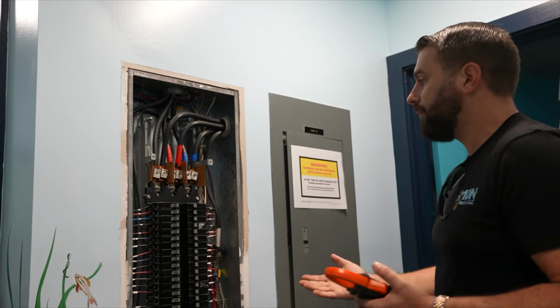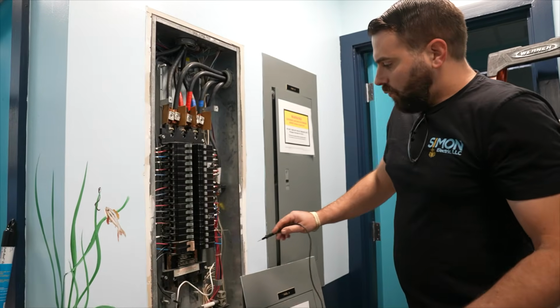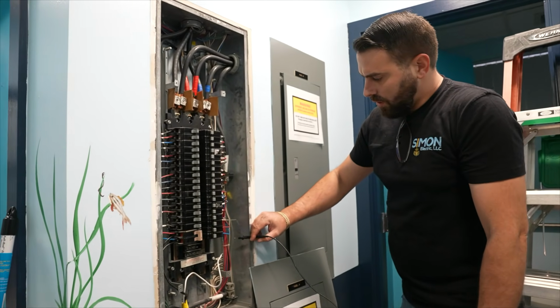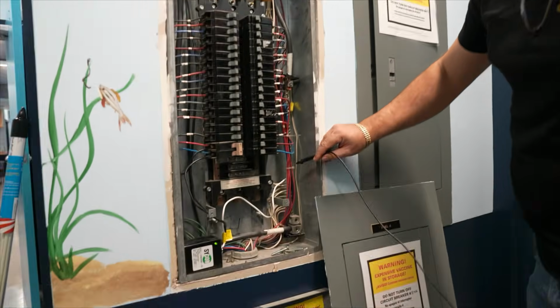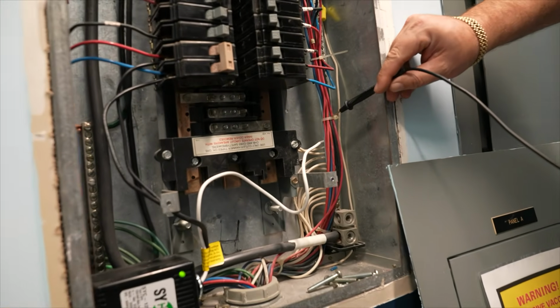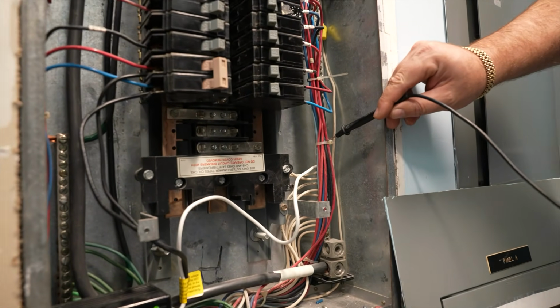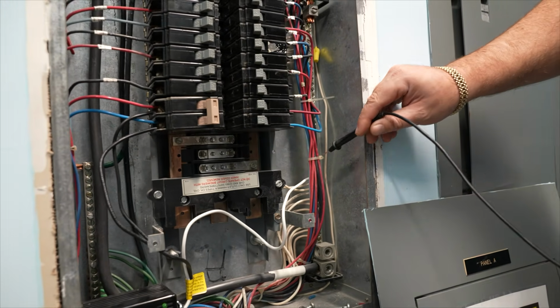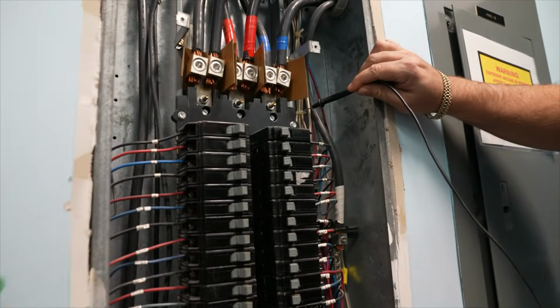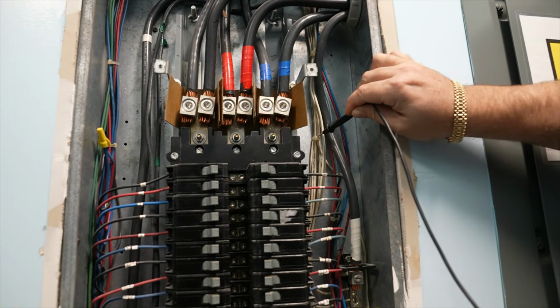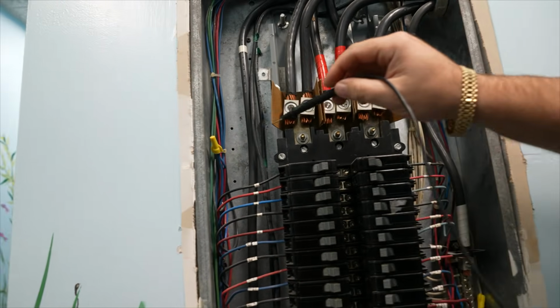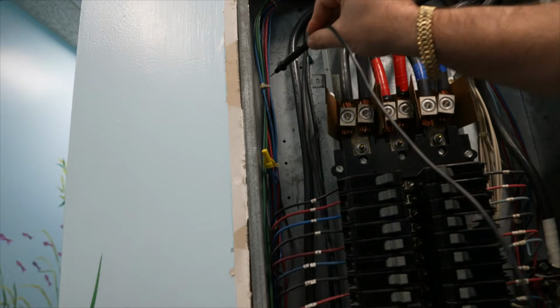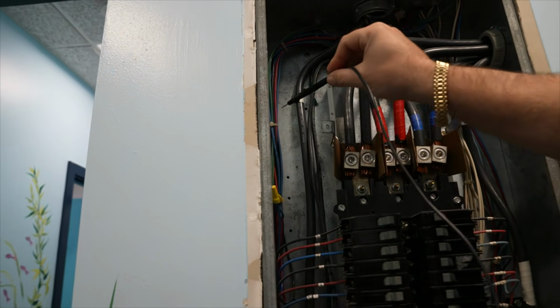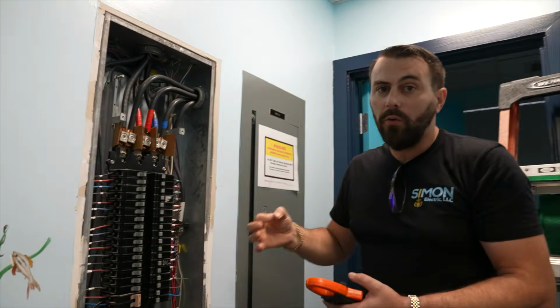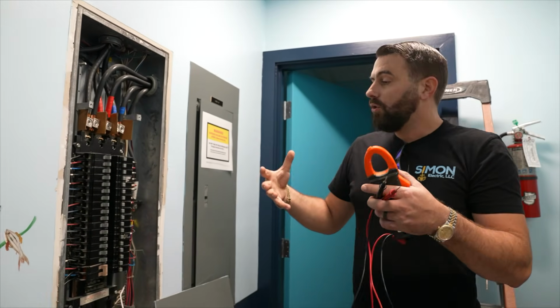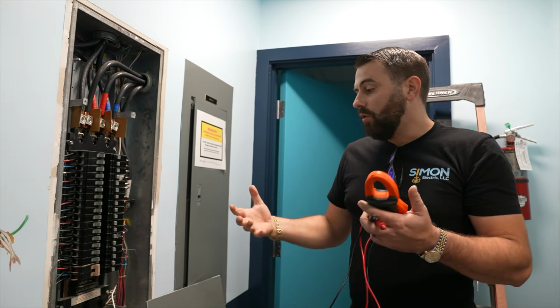But that's just a couple of the points in this panel here. One other issue I wanted to point out is that they have zip ties bundling hot wires. You're not allowed to bundle hot wires in a panel or anywhere for that matter. You're allowed to bundle neutrals, which is this white wire, so that one's okay, and you're also allowed to bundle grounds, which is these green wires. But you can't bundle greens with hots, or bundle multiple hot wires together - that creates a hot spot, and it's a code violation.